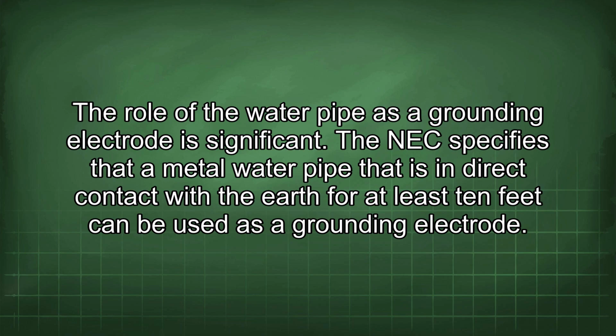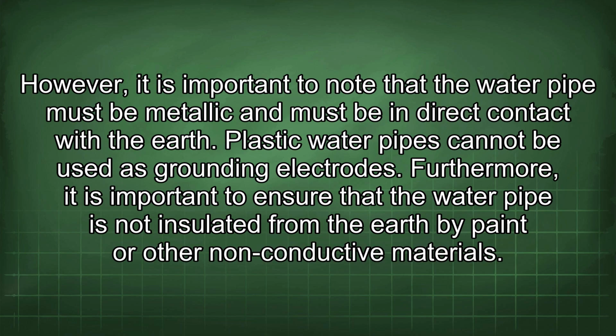The role of the water pipe as a grounding electrode is significant. The NEC specifies that a metal water pipe that is in direct contact with the earth for at least 10 feet can be used as a grounding electrode. However, it is important to note that the water pipe must be metallic and must be in direct contact with the earth. Plastic water pipes cannot be used as grounding electrodes.